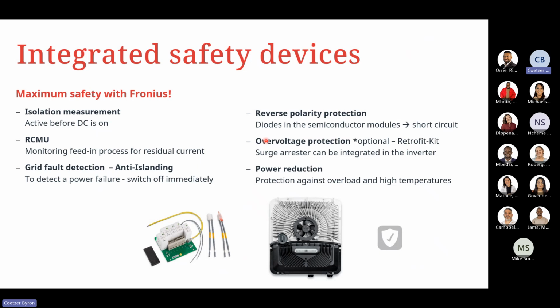So you do get your integrated safety devices. So again, the maximum safety with Fronius. The units will do an isolation measurement before DC is on. It always uses the last DC measurement that it had the previous day as a reference for when the DC is then switching on. So typically, if you've got a low PV voltage, you'll see something like 306 or 307. It could be triggered by an isolation measurement that's still taking place or is not completed yet.